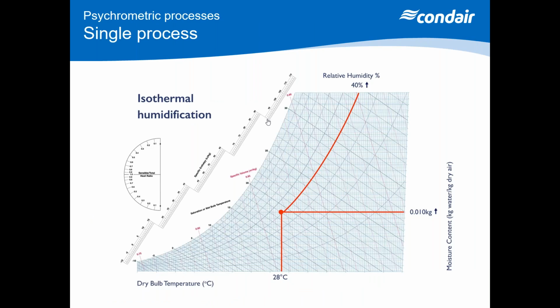So I want to go back to, if you're going to plot out the isothermal humidification, the first thing I want to do is increase my dry bulb temperature to allow that humidification to occur. So I need to increase my dry bulb temperature to my start condition. Once I've got my start condition, I can then isothermally humidify to get up to my set point.